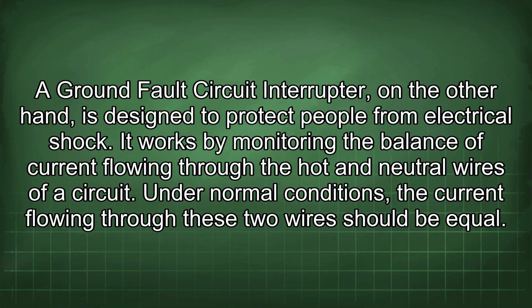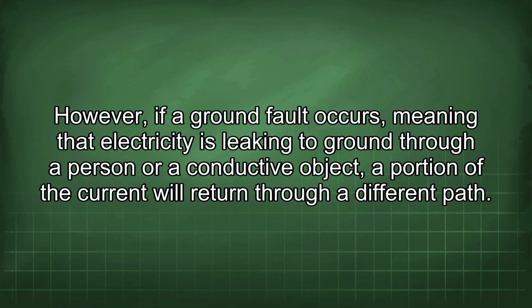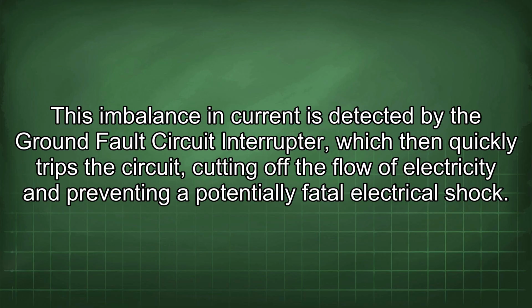A ground fault circuit interrupter, on the other hand, is designed to protect people from electrical shock. It works by monitoring the balance of current flowing through the hot and neutral wires of a circuit. Under normal conditions, the current flowing through these two wires should be equal. However, if a ground fault occurs, meaning that electricity is leaking to ground through a person or a conductive object, a portion of the current will return through a different path. This imbalance in current is detected by the ground fault circuit interrupter, which then quickly trips the circuit, cutting off the flow of electricity and preventing a potentially fatal electrical shock.